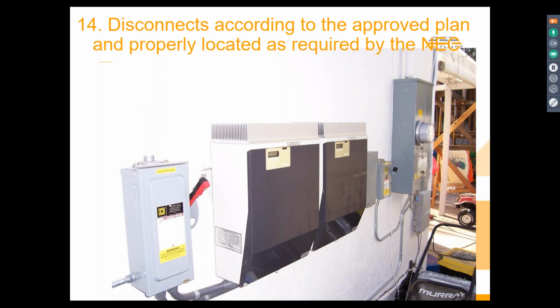All it's going to do is cause a problem in the field, because firefighters will think they're going to turn something off and they're not, and they're going to get shocked. And then everybody's going to be upset. So let's actually comprehensively deal with it - that's what rapid shutdown is. It's a comprehensive method of dealing with the process that actually turns stuff off rather than not doing anything.